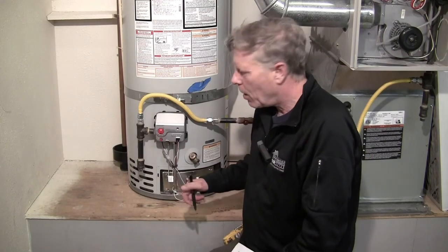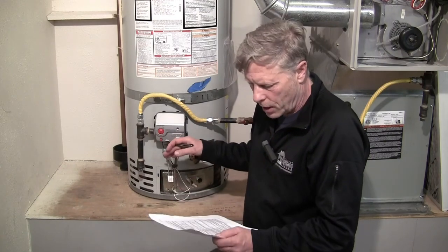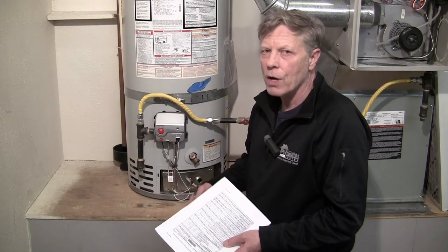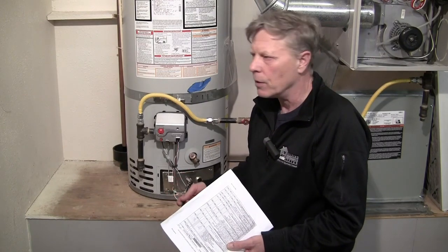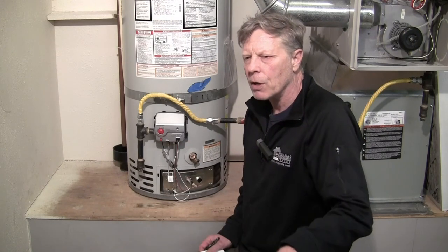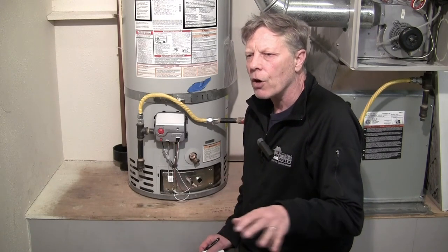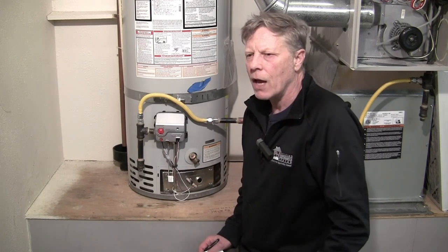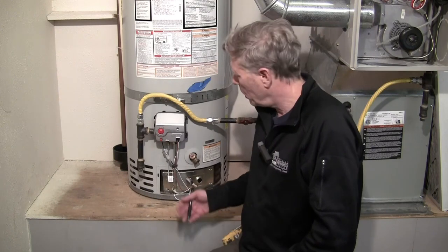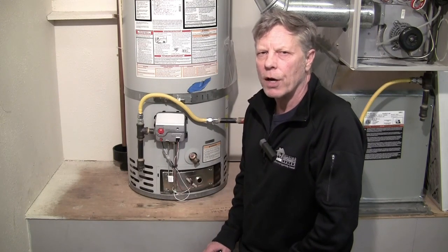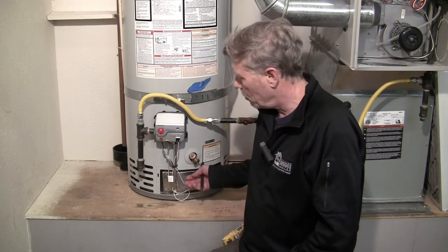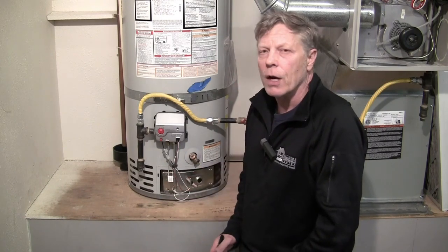4C is the water heater in a garage, and is it 18 inches off the floor, or is it FVIR listed? The reason water heaters in the garage are off the floor is because if your car leaks gas or your lawnmower leaks gas, the fumes from that can get lit off inside the water heater on the pilot light, and it can explode. It can explode out of the water heater.